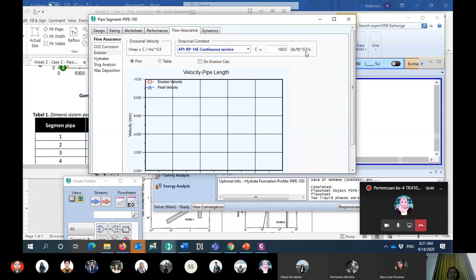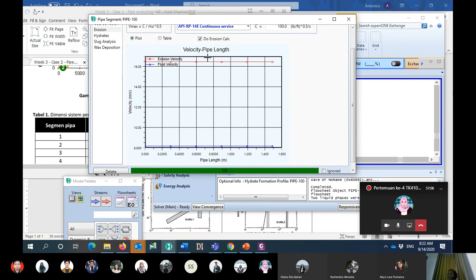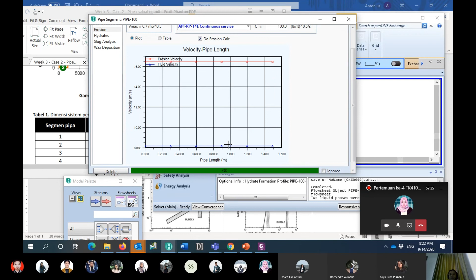This is the value, the critical superficial velocity, which is around 16, so it's close to 20 meters per second. But our operational superficial velocity is still at 8 meters per second. So it means that our current velocity is still safe because it is below the erosional velocity. Okay, so the erosional part is already done.